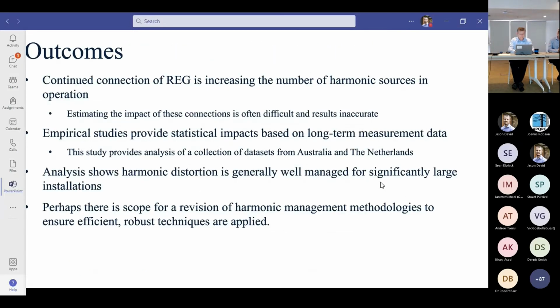Well, again, it's very difficult to provide absolute statements, but some discussion was had with the Dutch TSO. We were not given any specifics, but there are a number of potential impacts we may be visualizing here. One may be increased cancellation—more harmonic sources connecting to the network interact with each other and could bring down overall distortion, including passive componentry of individual installations acting as harmonic sinks for major harmonic orders, bringing down overall THD.